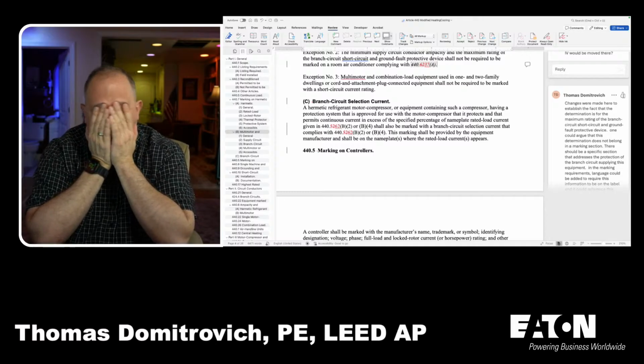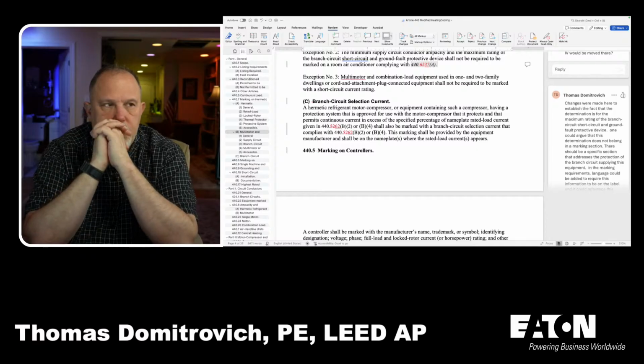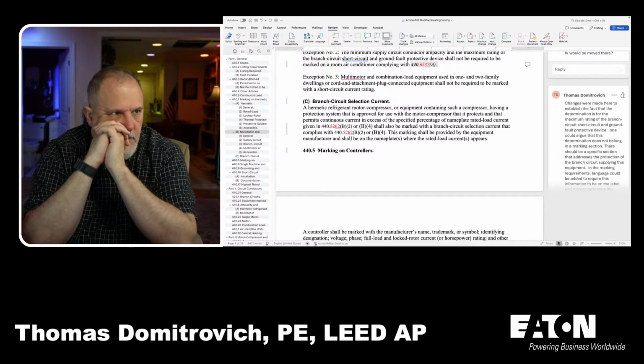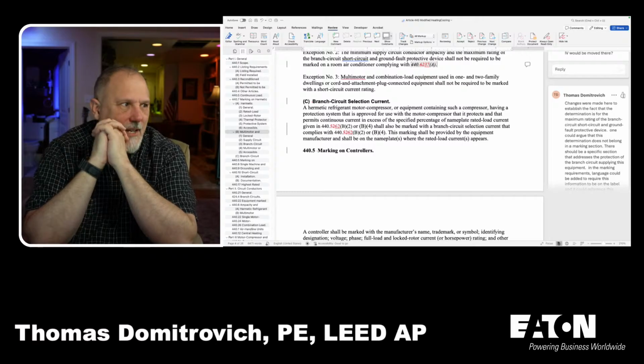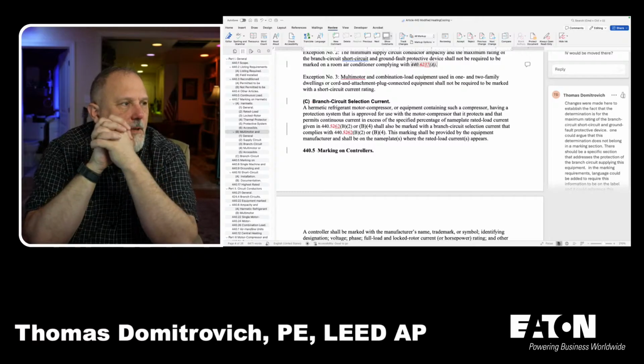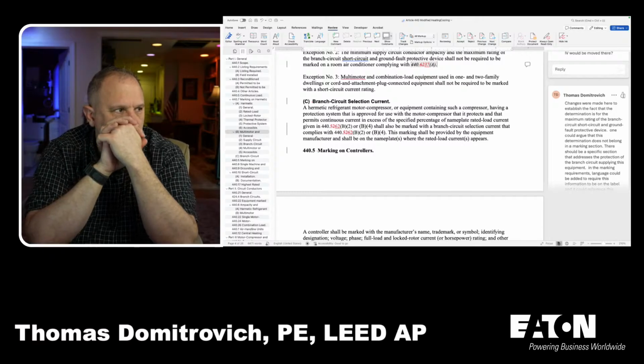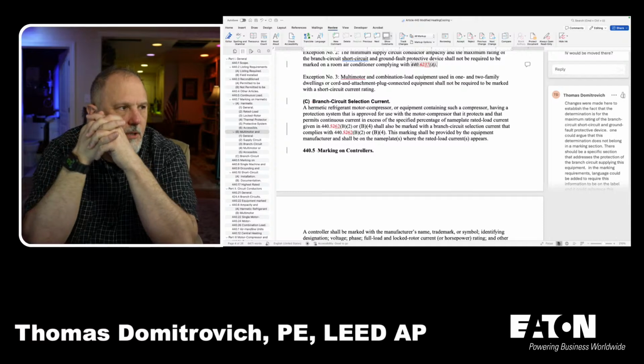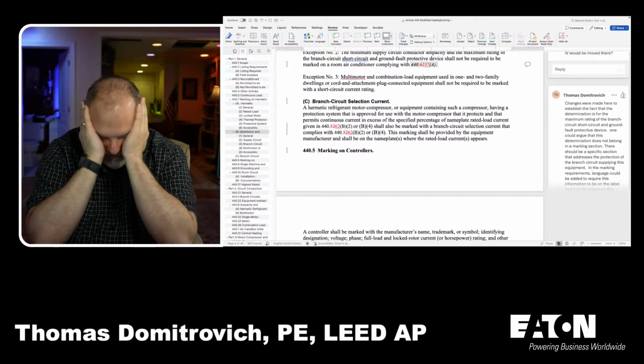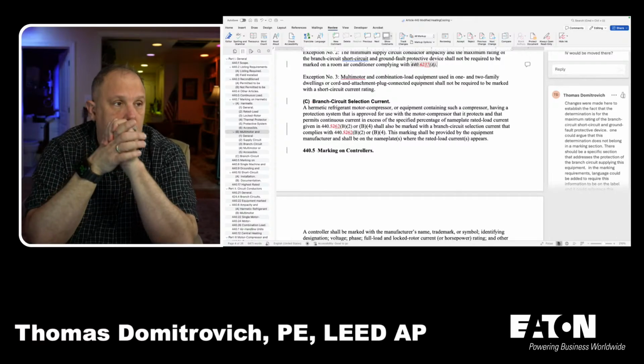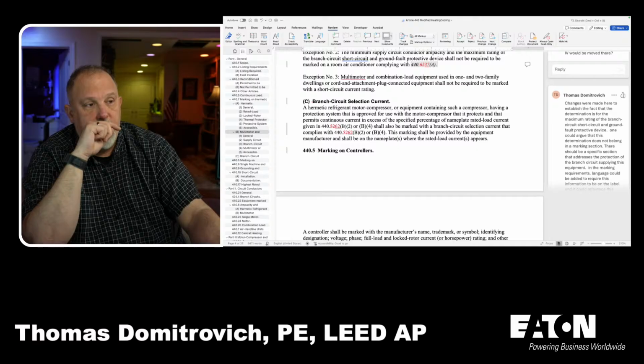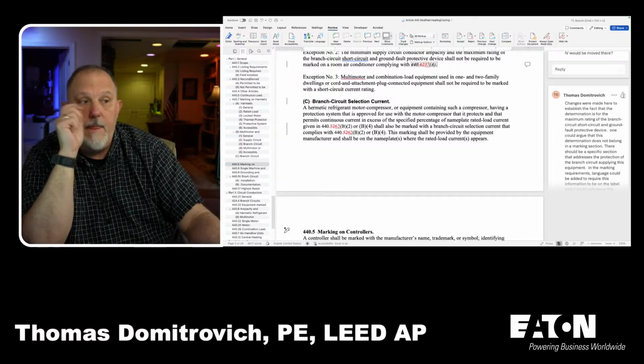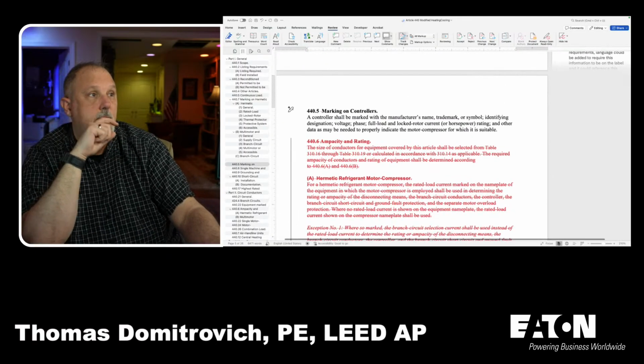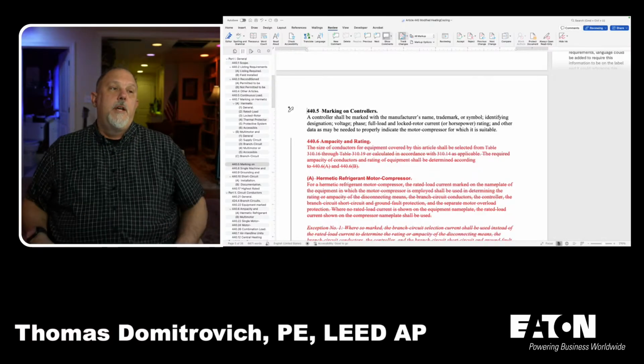Oh my God. This marking, hermetic refrigerant, having a protection that is provided, that protects, and that permits continuous current, shall also be marked. So this is a marking requirement. So it is a marking requirement. I'm not going to argue. If that's the way you want to roll, then that's the way you want to roll. All right, putting track changes back on.